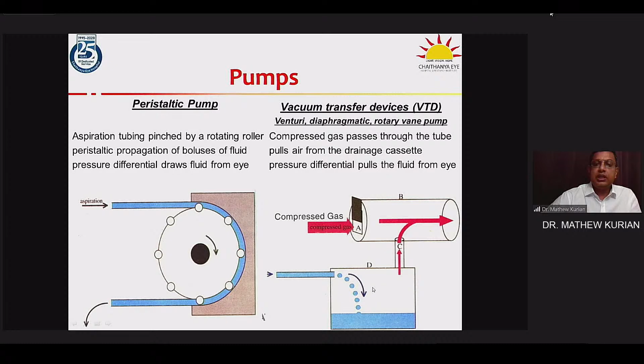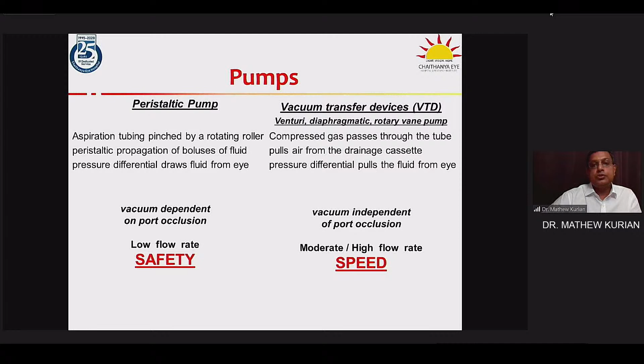Conventionally, the original machines, let us say the Universal 2, the vacuum was dependent on port occlusion. It was a slower machine and it was credited with more safety. The vacuum transfer devices like the Venturi, the Star's original machines, were more vacuum independent, and they had higher flow rates, and so they were associated with speed. But companies have looked at the other technology and have tried to pull in features from the other technology.